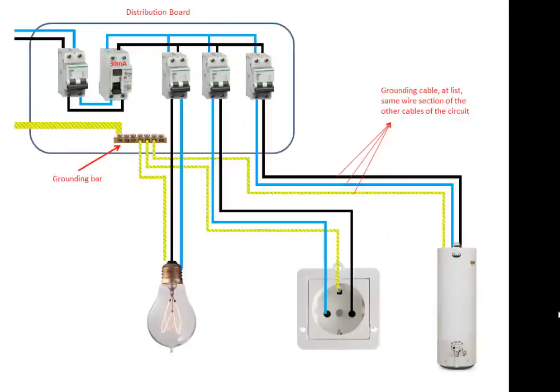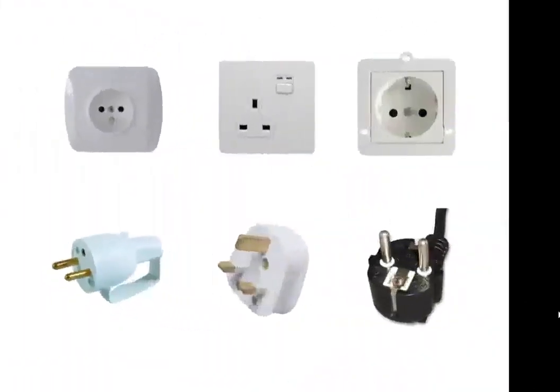In each secondary circuit, the grounding wire should reach the sockets and lights along with the phase and neutral. The grounding cable should always be yellow and green. The size of the grounding wire in the secondary circuits should be at least the same size of the neutral and phase cables. We should make sure the grounding cable reaches all electrical equipment. To ensure this, all sockets must have 2 poles plus grounding, as we can see in these examples. The plugs and sockets of the installation should be of the same kind. UK plugs for UK sockets, French plugs for French sockets, and so on. Otherwise the appliances won't be grounded.